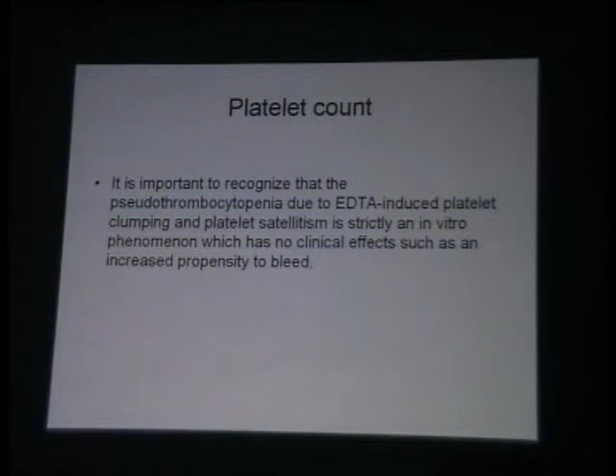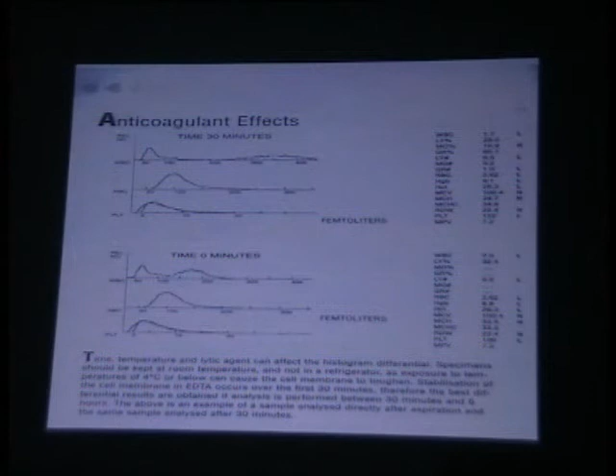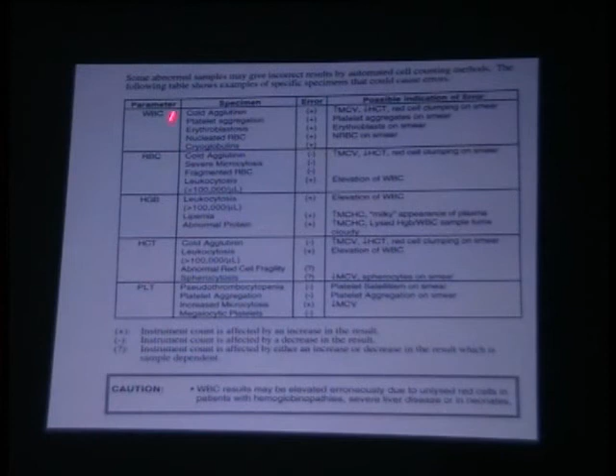Next, please. Another very important point, the people who are using counters must realize, they take the sample, put it quickly in the machine, and get a quick result within 10 minutes. Please remember that at 0 hours, your WBC stabilization may not affect your RBC and platelets, but it will definitely affect your WBC differential, because to stabilize that membrane, it takes half an hour. Look at this span, it is finishing at 200 femtoliters, whereas a good 30 minutes count gives you a proper lymphocyte peak, mid-population and a spread of 400 femtoliters. If you are looking at your differentials from your counters, please give half an hour before you can interpret the differential count. Next, please.